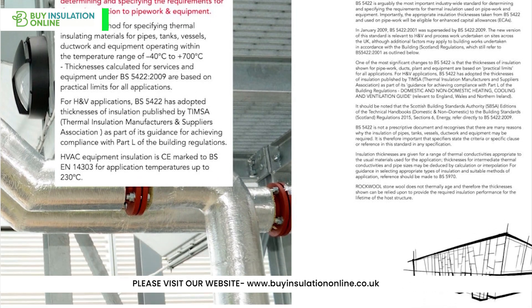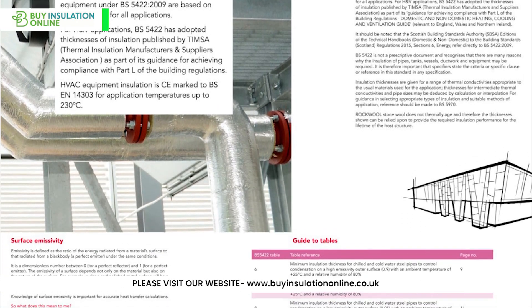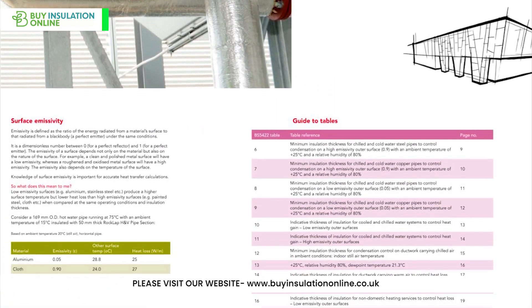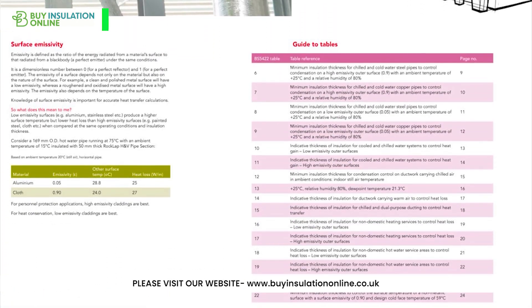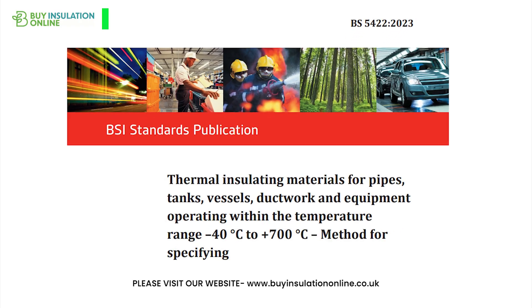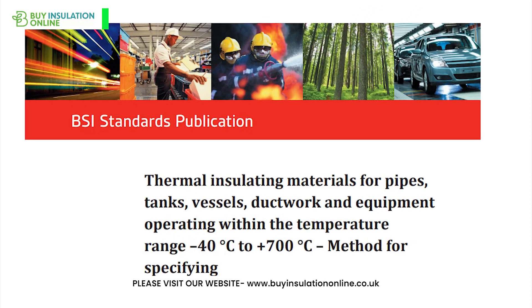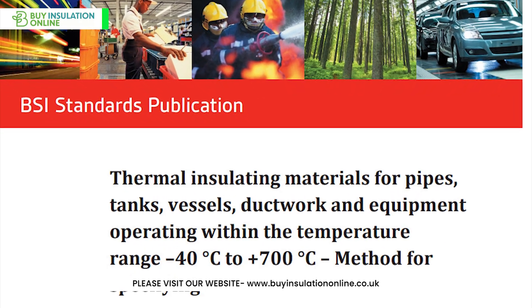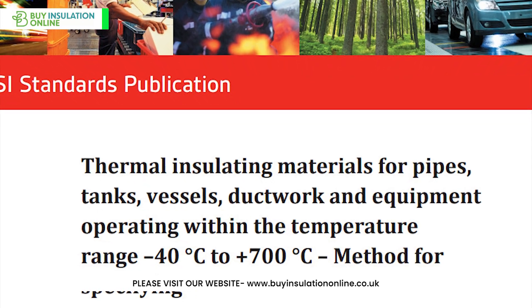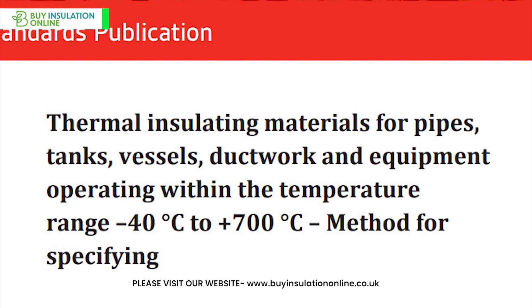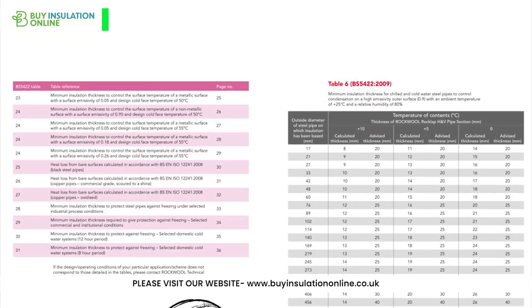British Standard 5422 plays a key role in decisions surrounding pipe insulation thickness. This standard provides guidelines for thermal insulating materials for pipes, tanks, vessels, ductwork and equipment operating in the temperature range of minus 40 degrees Celsius to plus 700 degrees Celsius.